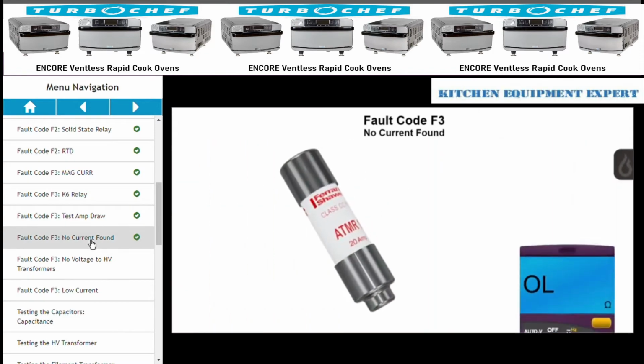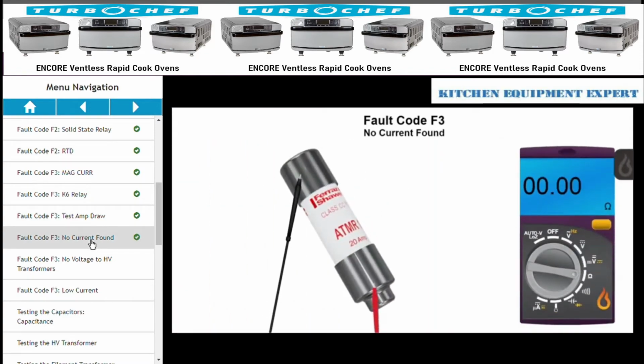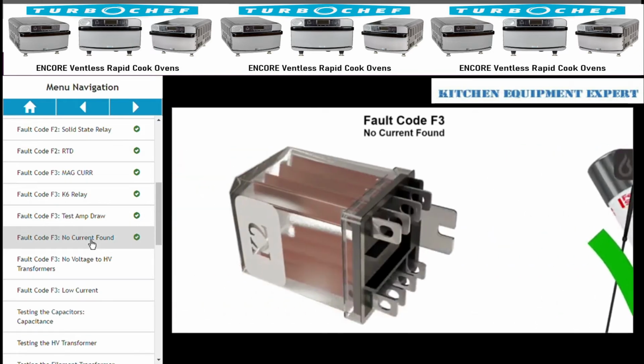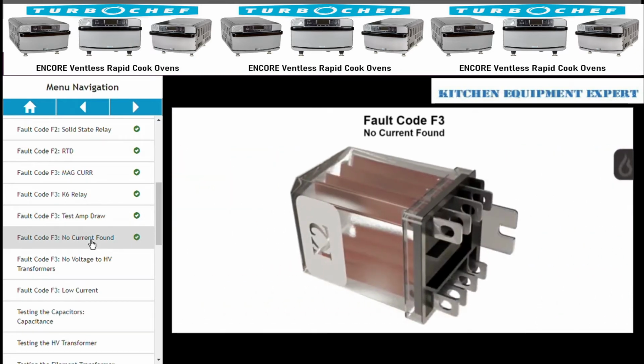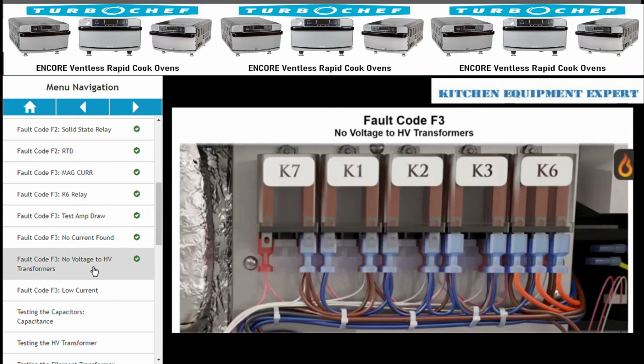First, check the F3 fuse to see if it's blown. If the fuse is okay, check the K2 relay to see if it's actuating. There's no voltage present at the high voltage transformer. Check the K2 anode relay.